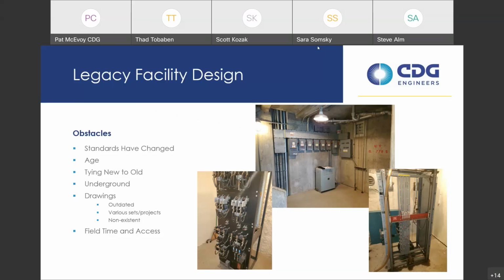One issue we always run into with legacy installations is whenever we do something underground - that's always a big area we've got to watch out for. Electrically, we run a lot of stuff underground. If they have a duct bank or want to put in medium voltage cable underground, they might directionally bore it or trench it.